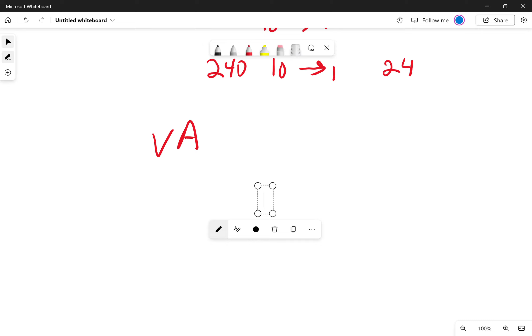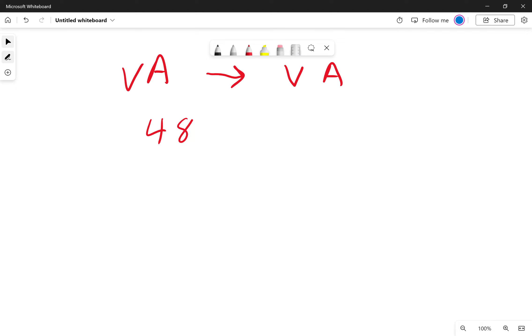A transformer has to have the same number of voltamps going in on one side as it has coming out on the other. So if we look back at that first problem, where we had 480 volts with a 2-to-1 step down to 240 volts, if this is 48 kVA, 48,000 voltamps, then we're going to have 48,000 voltamps here as well.